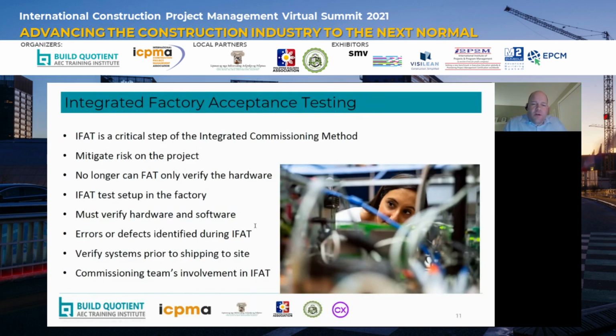Another two points that are critical during IFAT: it's really good to get the operators, the end users of the product, involved during IFAT. Typically what's been done in the past, which no longer works, is the operators may see a screenshot of the HMI screens and they're asked to review them. The problem with that is that they don't get to see the functionality of the system as well. IFAT is a great opportunity to have them involved. If they can see the HMI screens, if they can actually interact with them and see the function of them, that's the time to get the operators' input, because changes are much easier made during IFAT.